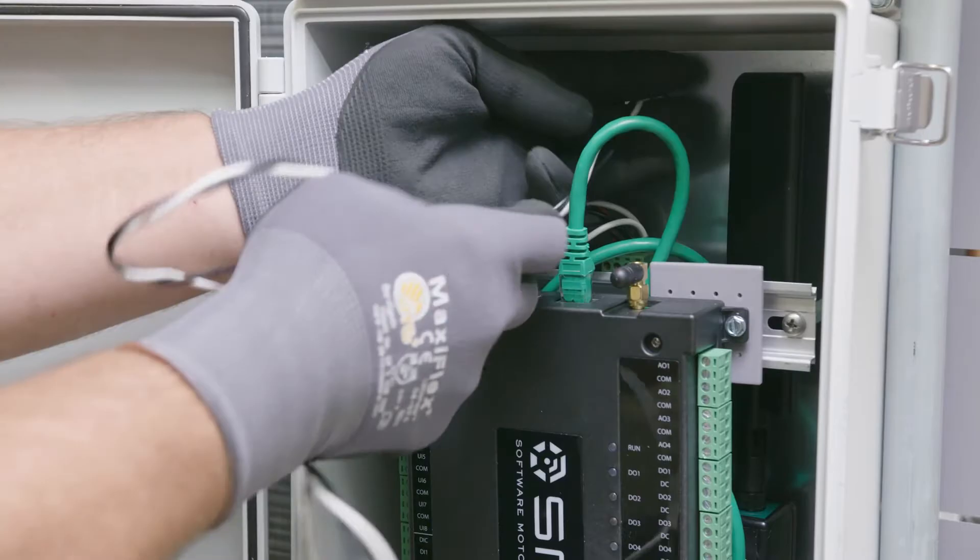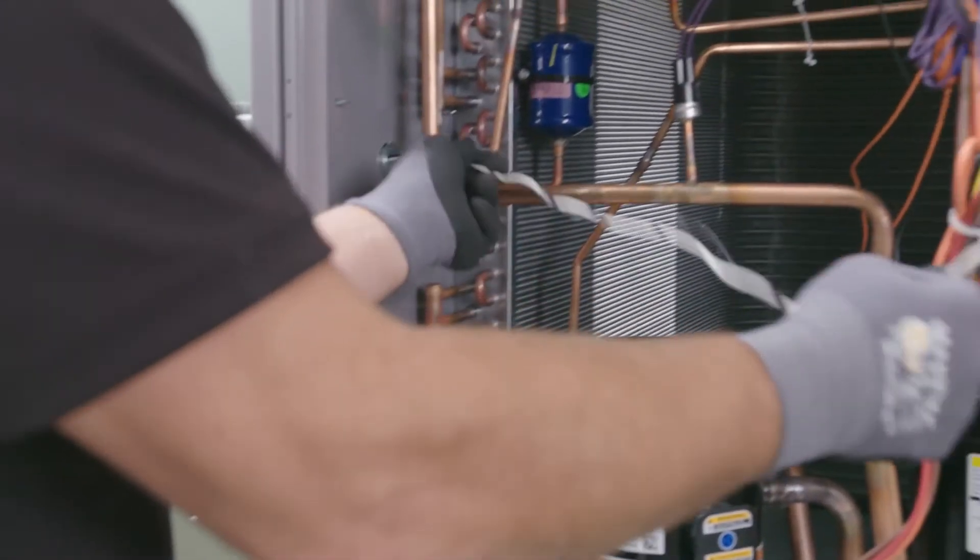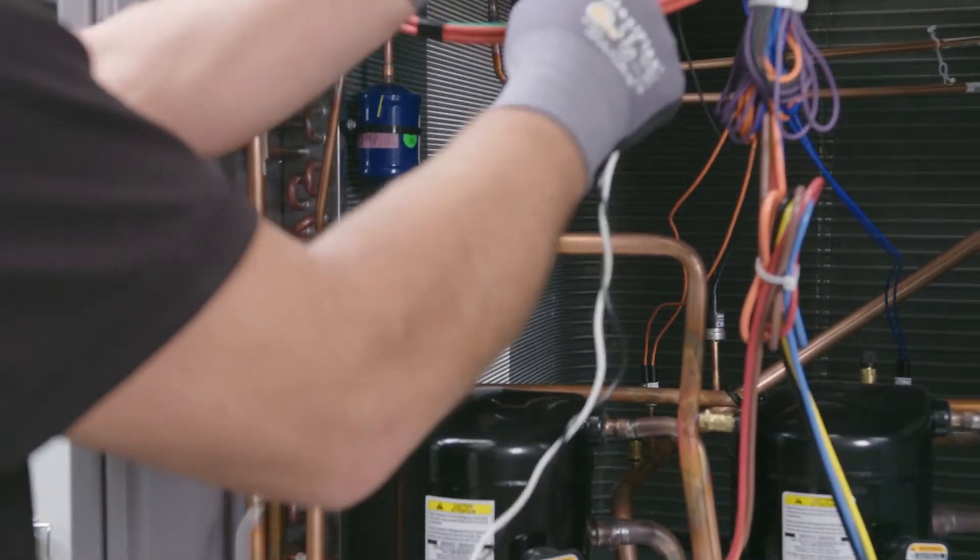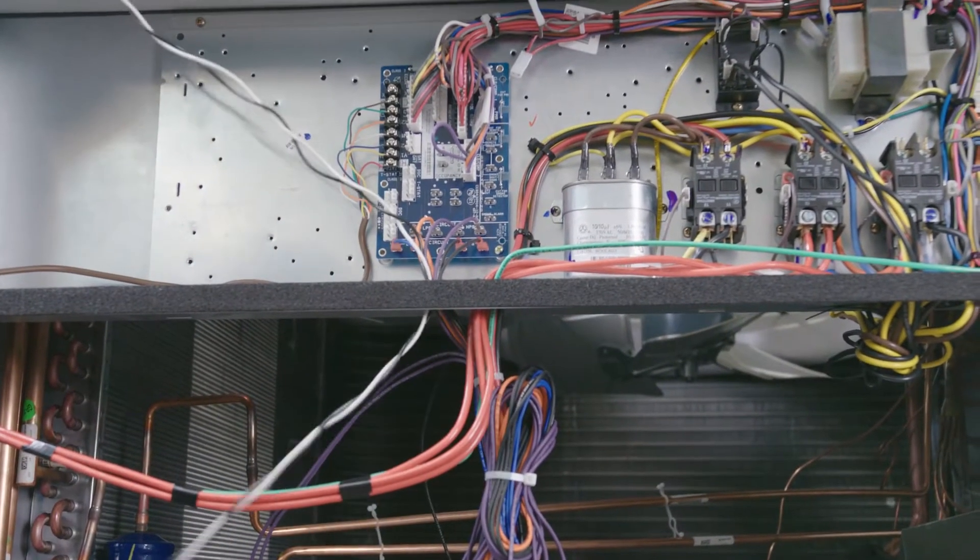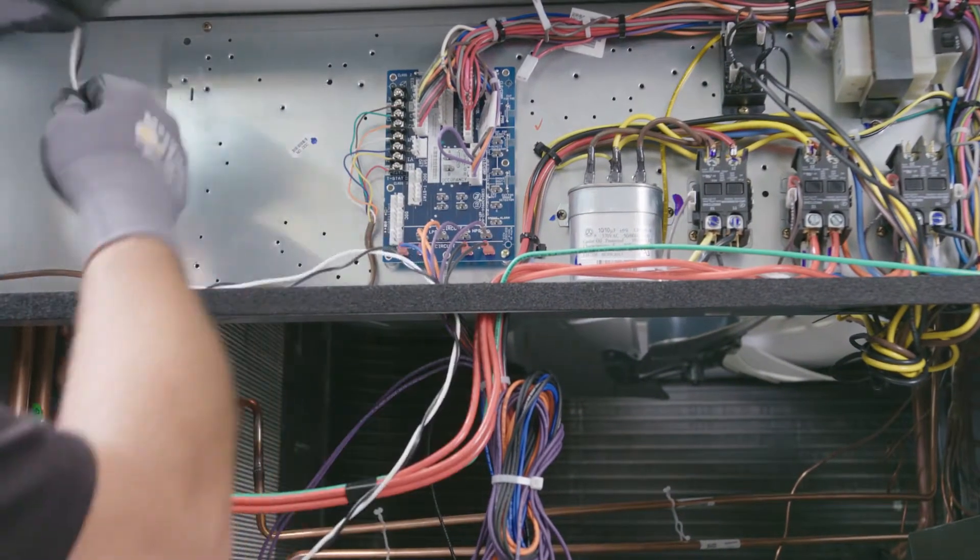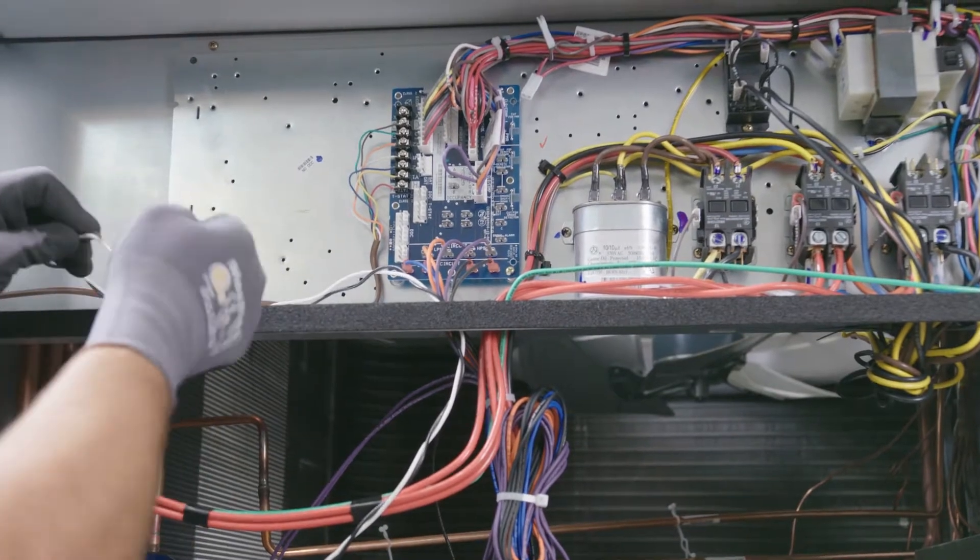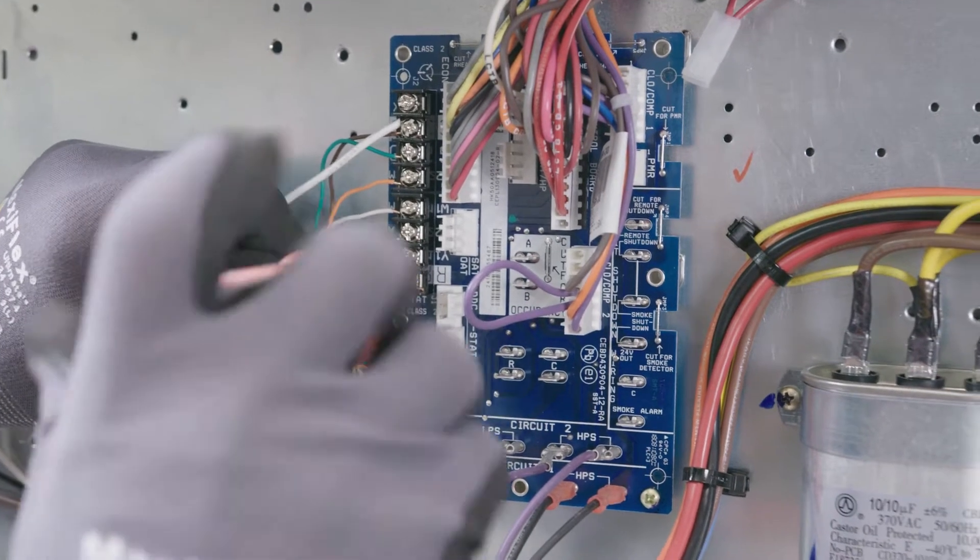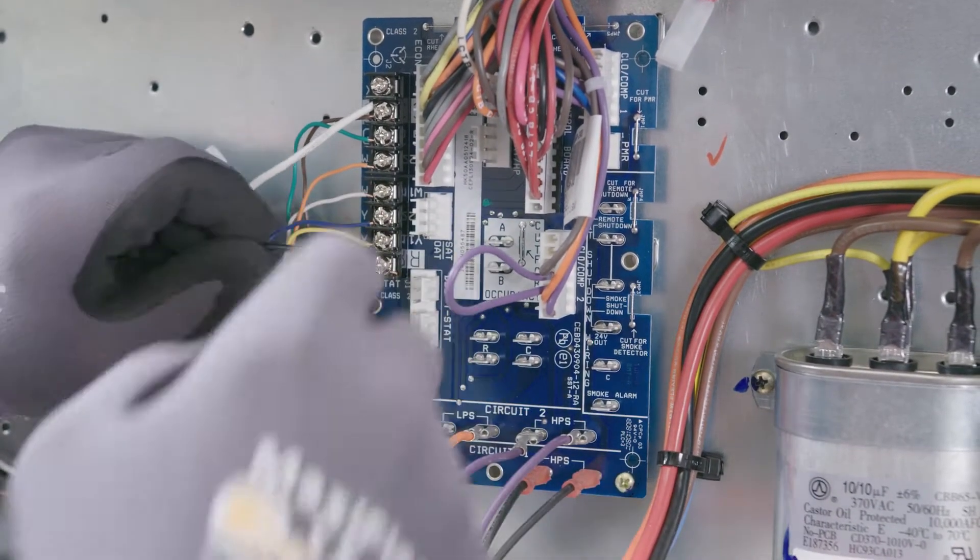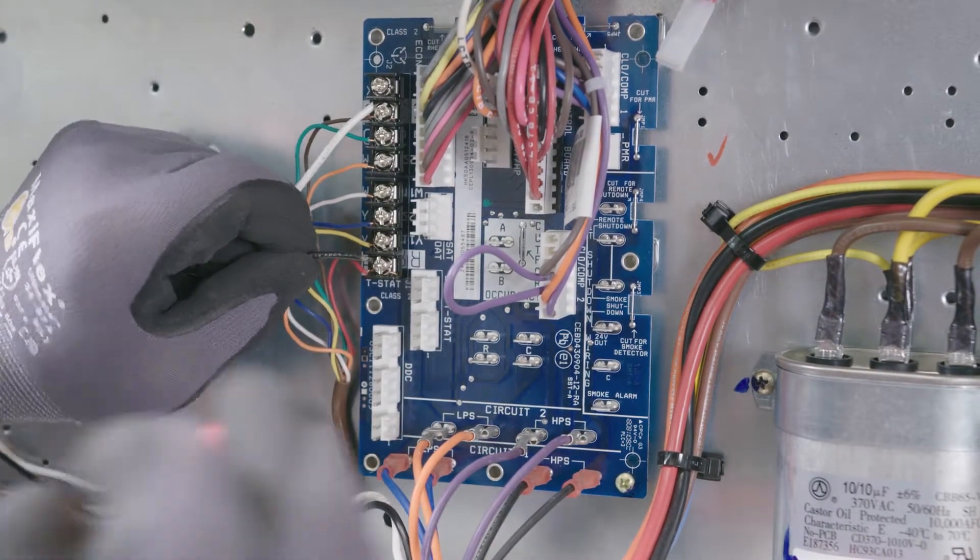Now that you've got the panel mounted, you want to pull out the black and white wires, which is the 24-volt power supply to the SMC panel. Simply run the black and white wires to the unit transformer or to the terminal block on the unit. Once you've run the 24-volt power supply for the weatherproof enclosure panel to the unit, simply terminate it on the C and the R terminals to power up the panel.